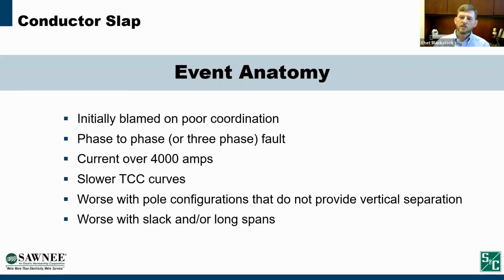So when we looked more closely at this conductor slap phenomenon, we initially blamed it on poor coordination. Before we had the oscillography data from the interrupter and all the event log data that we got, we thought we just had poor coordination. Even though our TCCs looked good and they appeared to coordinate, we couldn't detect that secondary fault upline. So we thought that they just didn't coordinate, or that downline device was just not operating fast enough because of a mechanical issue.